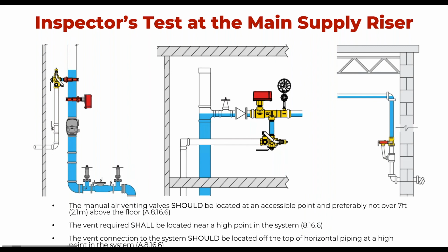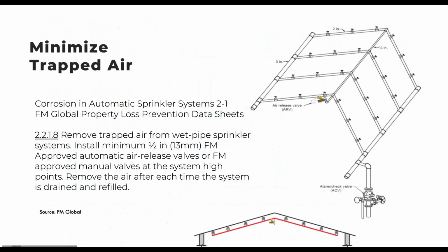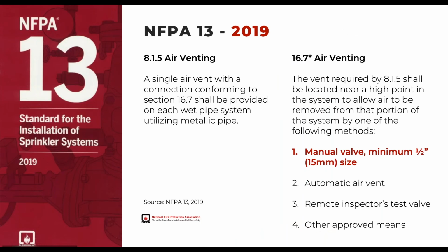So the water systems fill like a pool. Once the water drops down to that drain valve, it's trapping all the air above it. Again, where these things are recommended to be installed is near a high point in the system. You only need one per system. You could put gang vents in where you have tying all of your branch lines into one to remove the most air. That's off of an FM drawing, not a requirement.